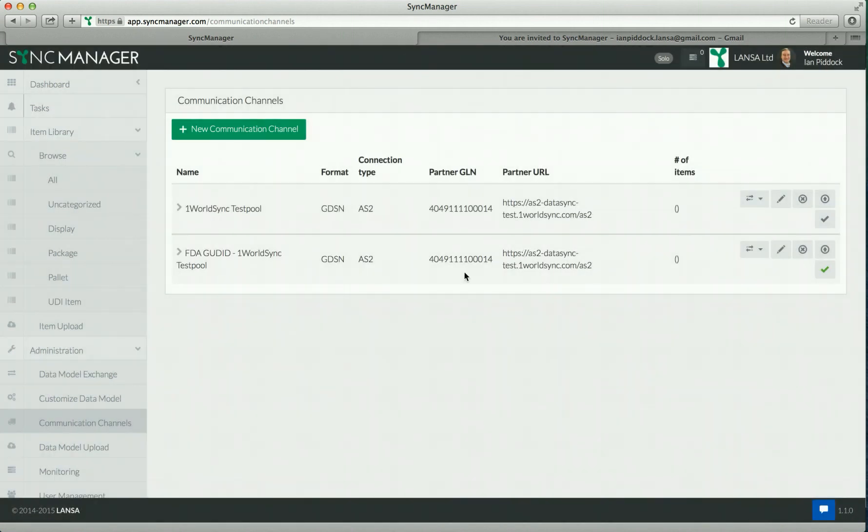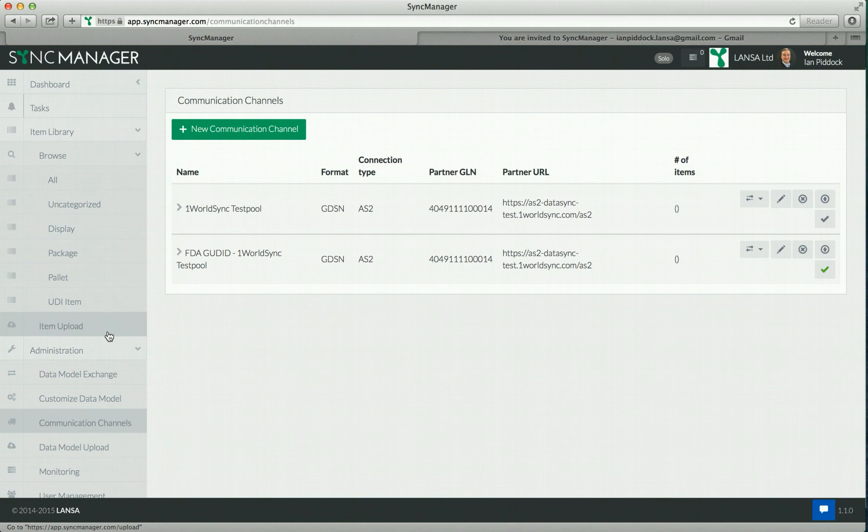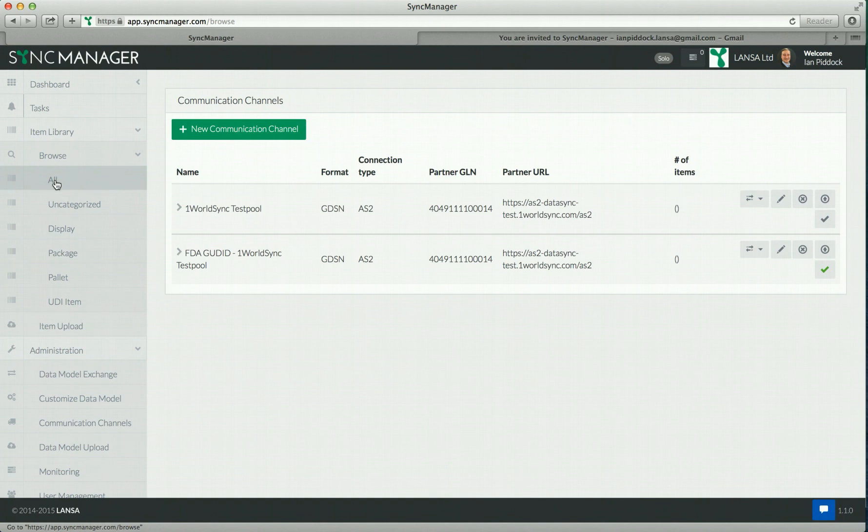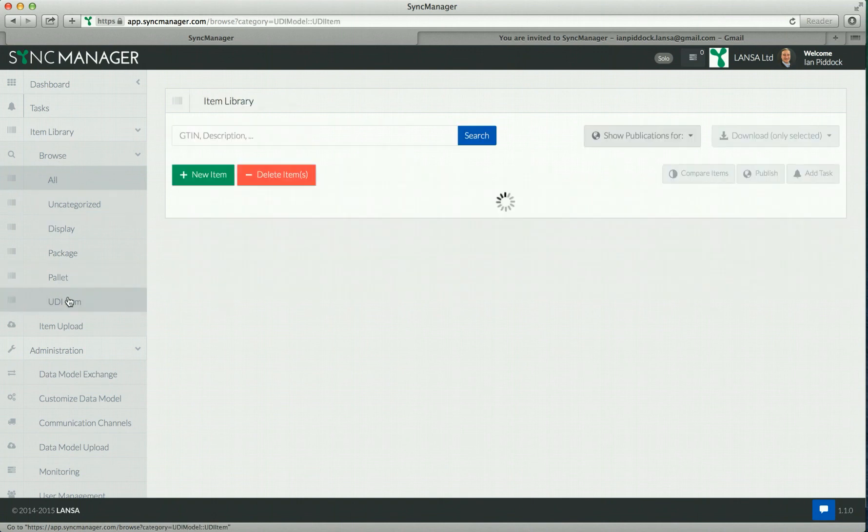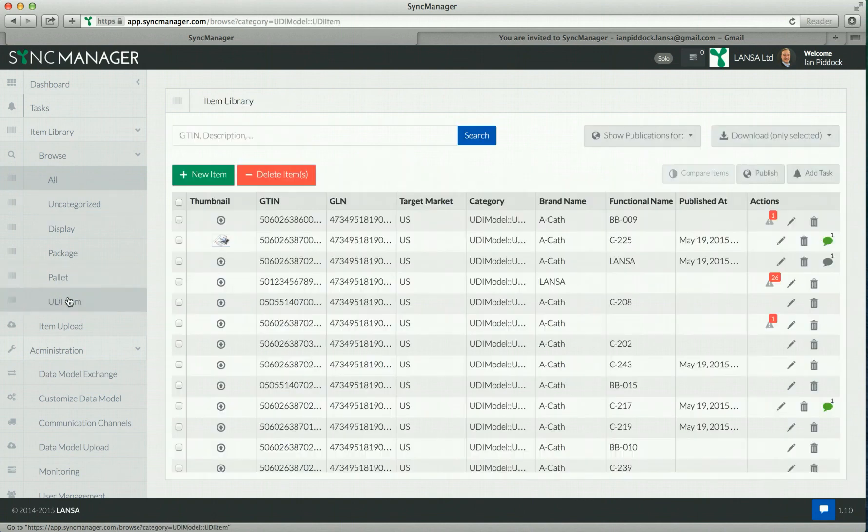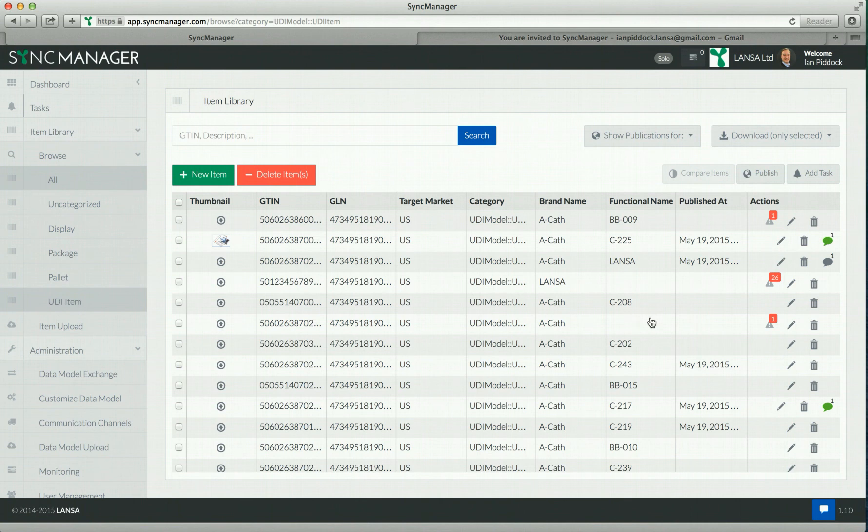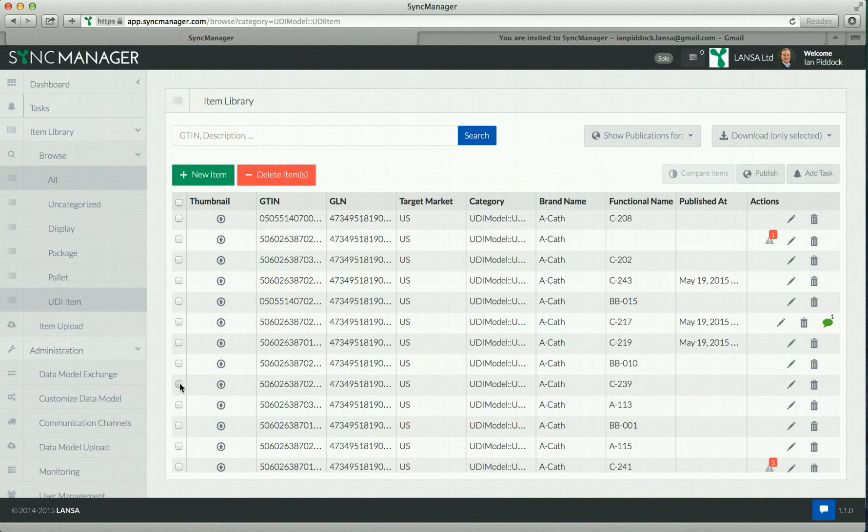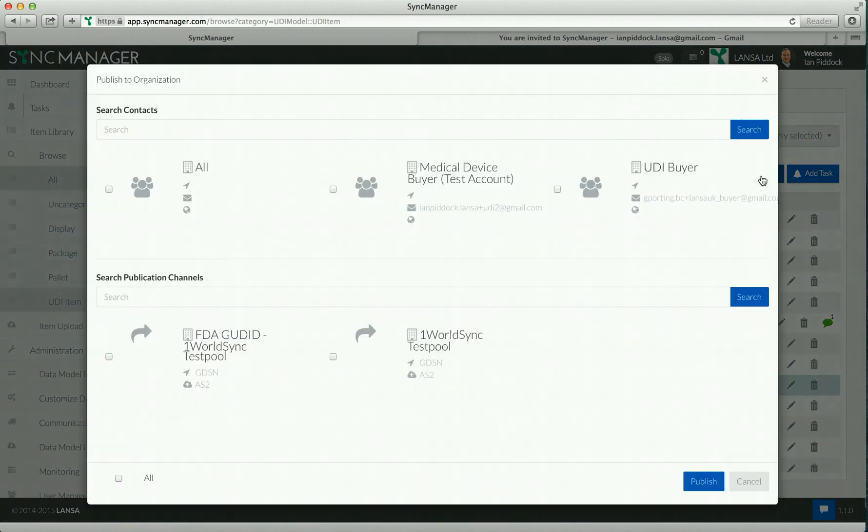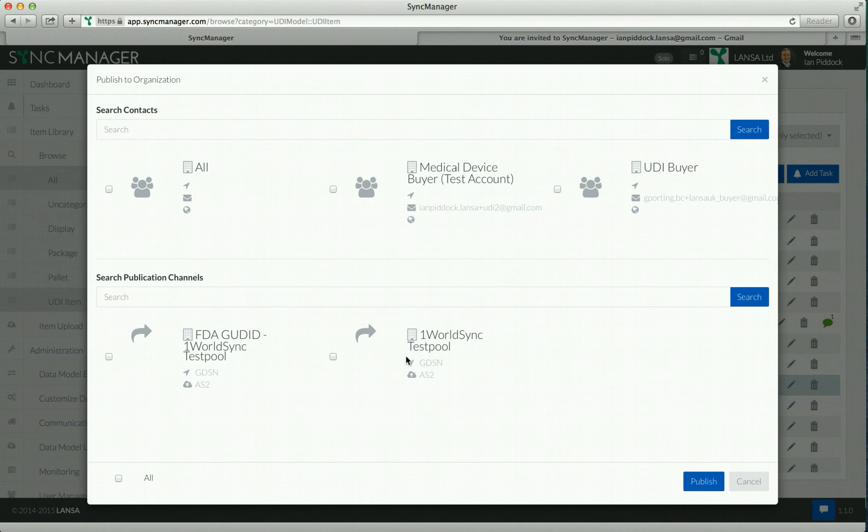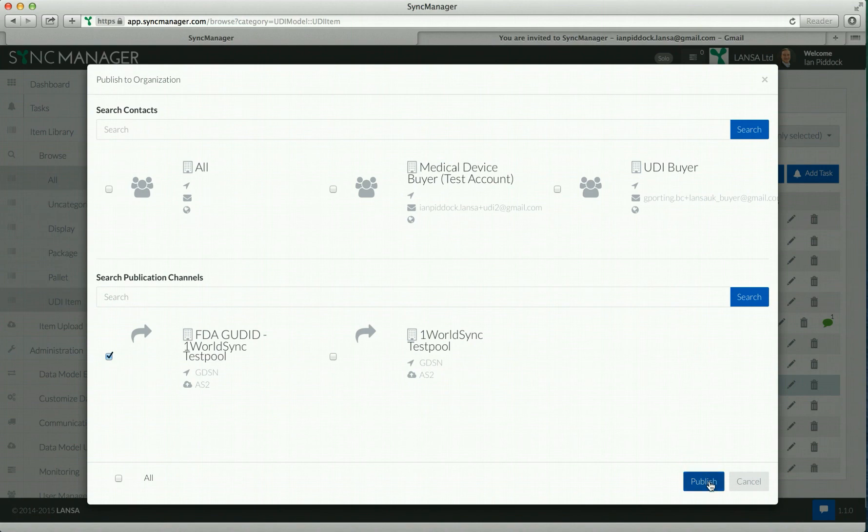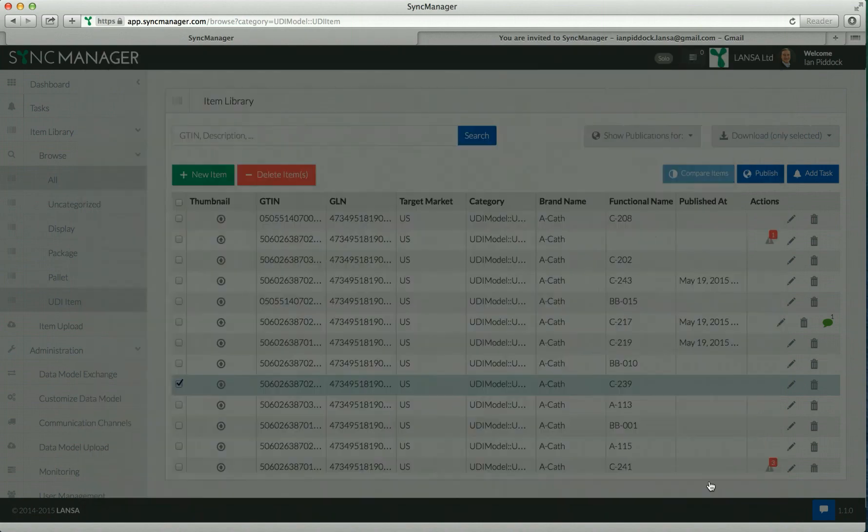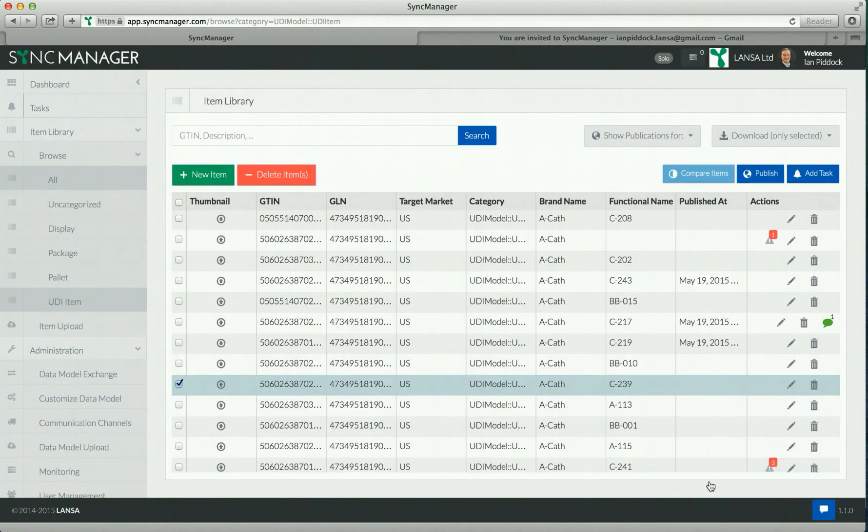I'm going to show you how to publish an item using one of these communication channels. If I go back to my item list, my UDI items, let's select an item to publish. Let's go to this C239. I'm going to select that item and publish. Now I'm going to select the FDA GUDID. This is going to do a publish to the GUDID. Click on publish.